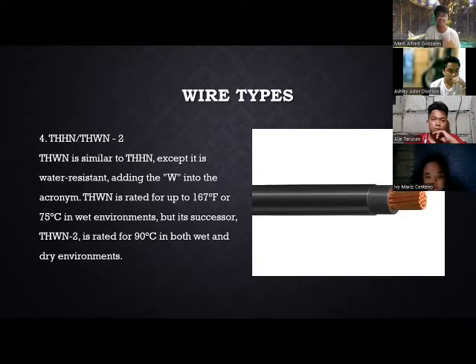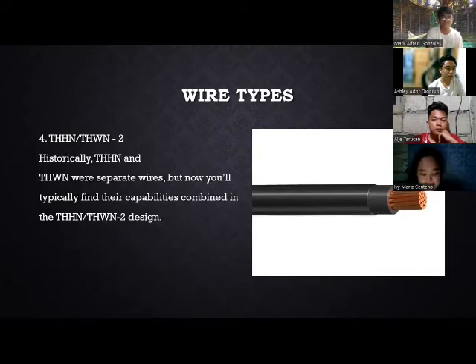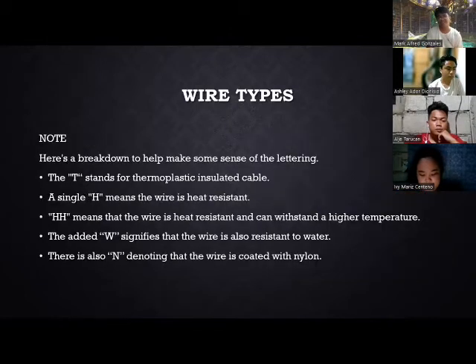Ang THHN or THWN2. THWN is similar to THHN, except it is water resistant, adding the W into the acronym. The THWN is rated up to 167 degrees Fahrenheit or 75 degrees Celsius in wet environments. But its successor, THWN2, is rated for 90 degrees in both wet and dry locations. So yun ang ginagamit. Historically, THHN and THWN were separate wires, but now you'll typically find their capabilities combined in the THHN, THWN2 design.